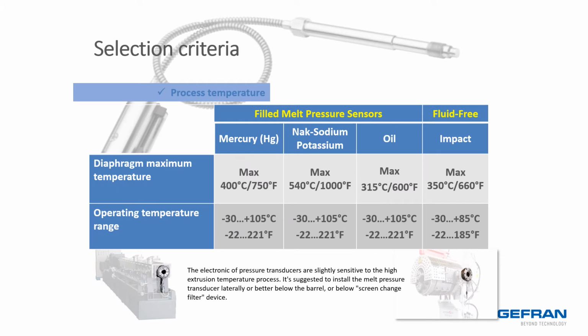As this slide illustrates, mercury is good up to 400 Celsius. The FDA-approved oil is good to 315 Celsius. The sodium-potassium fill is good up to 538 Celsius with the right diaphragm. The contact medium may suggest a different diaphragm material or thickness. Required accuracy and observed temperature drift will demand attention in the selection process too.